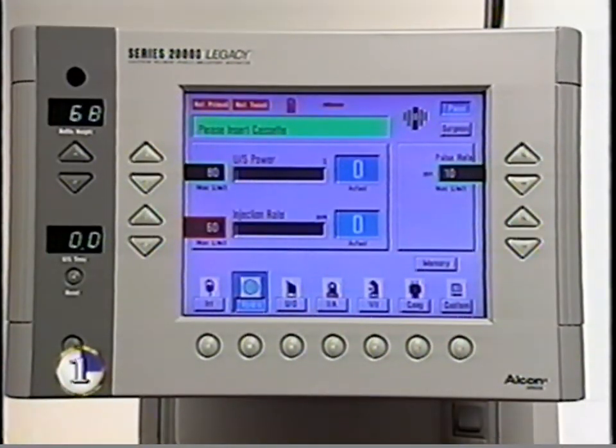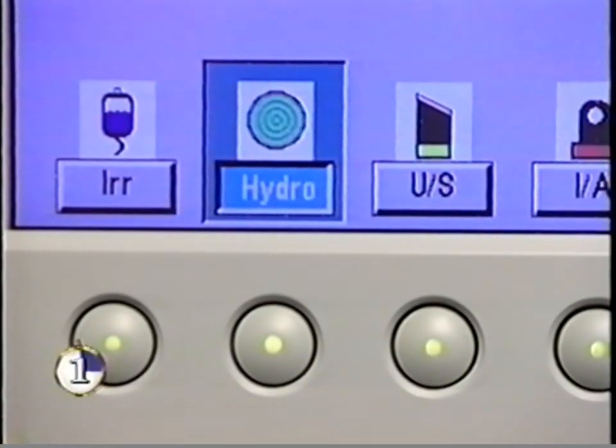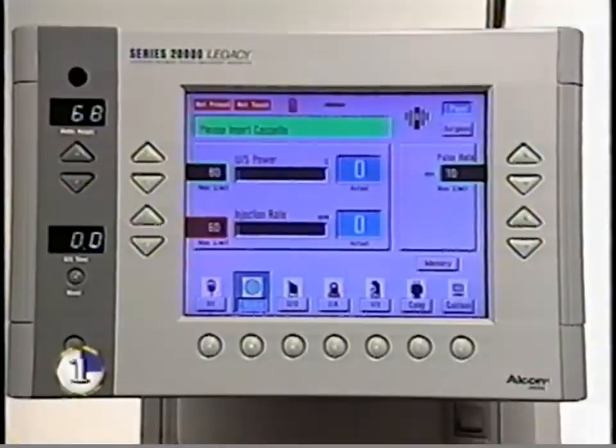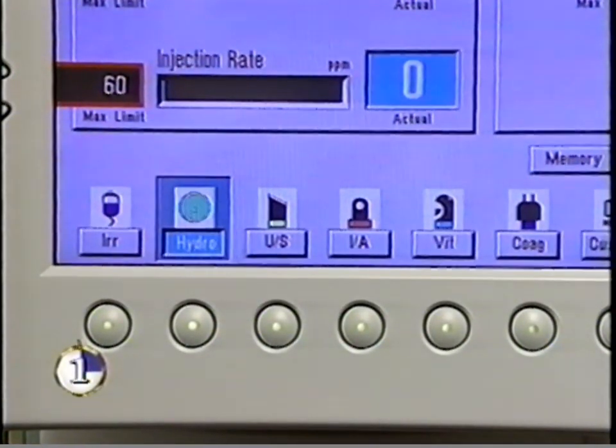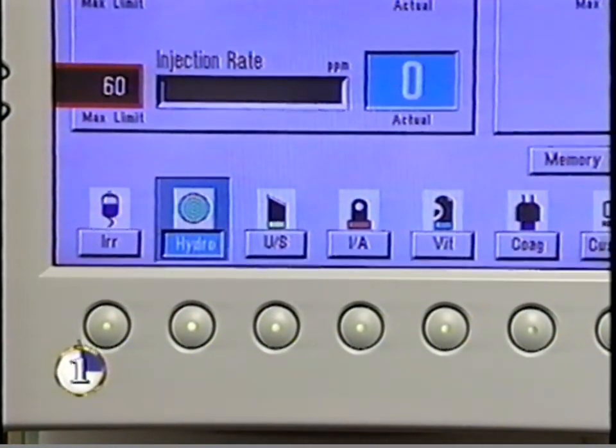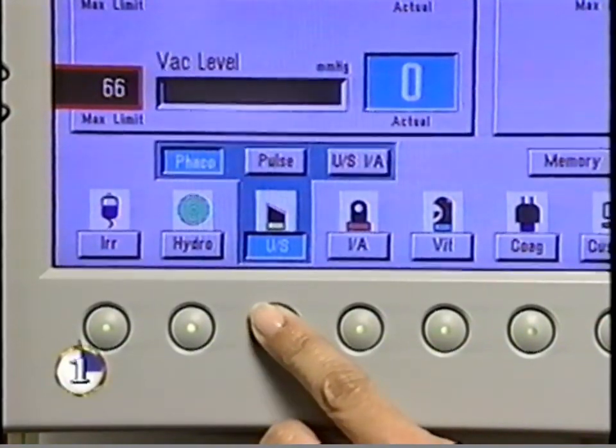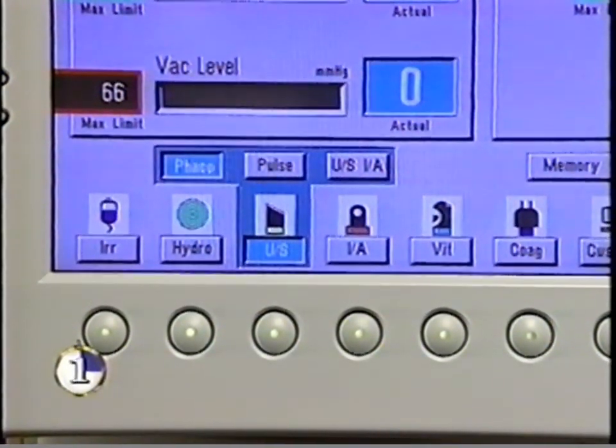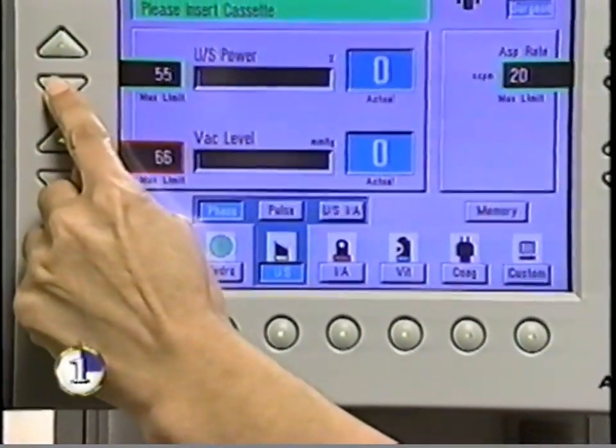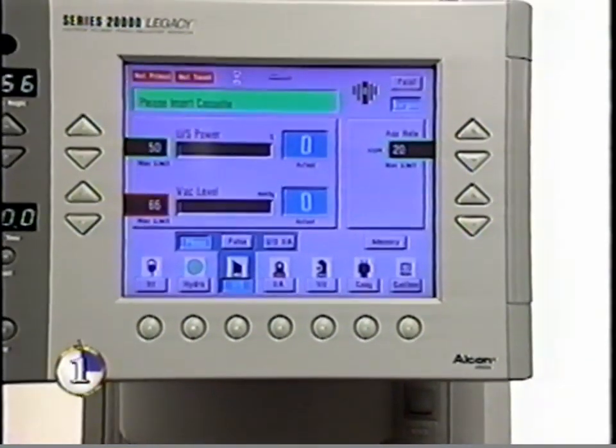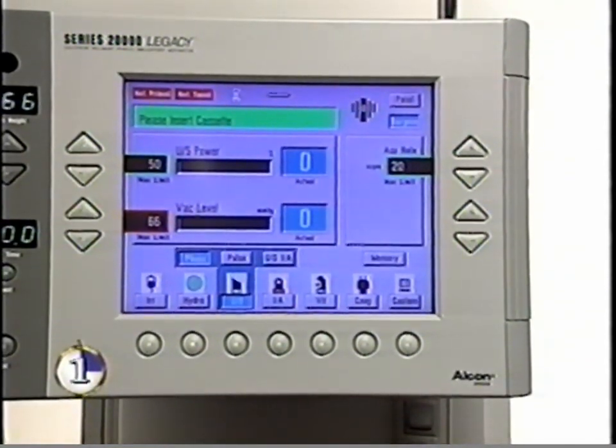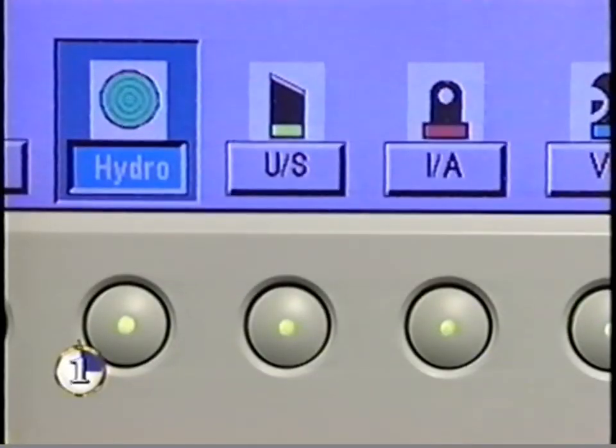The hydrosonics handpiece is used to pre-soften the cataract prior to phacoemulsification. In this mode, the primary parameters are injection rate and ultrasound power. Pulse rate is the secondary parameter. Ultrasound mode is used for performing cataract emulsification and aspiration. Ultrasound power adjusts in 5% increments. Both panel and surgeon control may be enabled in this mode and its submodes.